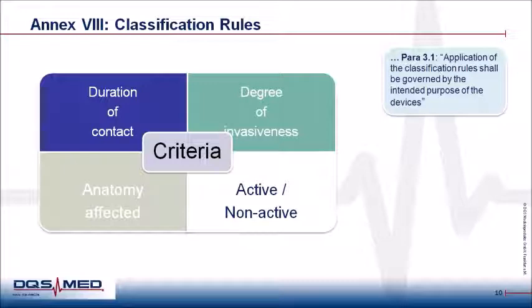The medical device classifications are based on the vulnerability of the human body and should take into account the potential risks associated with the technical design and manufacturing of the device. These rules can be found in Annex VIII of the MDR. According to Chapter 1 of Annex VIII, there are 4 criteria laid down by the MDR for classification of the device. Firstly, duration of contact. Secondly, degree of invasiveness. Thirdly, the anatomy affected by use of the device. And lastly, whether the device is an active device or non-active device.